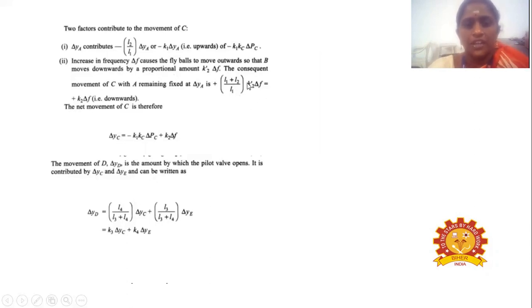Okay. To K2 del F equal to, that is plus K2 del F, because here the positive sign indicates that it moves in the downward direction. So the net movement we can write as del YC equal to minus K1 Kc del Pc plus K2 into del F. So the movement of D, that is del YD, is the amount by which the pilot valve opens. So it is contributed by del YC and del YE, and we can write like this.